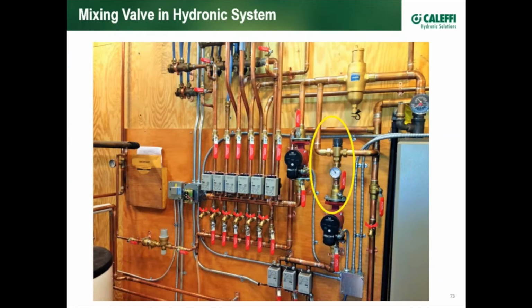Not all mixing valves, of course, are used in plumbing systems. Hydronics is a very common application. Maybe 30% of our business is hydronic, such as this one. Always pump away on mixing valves rather than pump into the hot or cold return ports. Pump away, that keeps them nice and stable. In this case, a fixed temperature is being delivered to three zones controlled by the Caleffi zone valves down here.